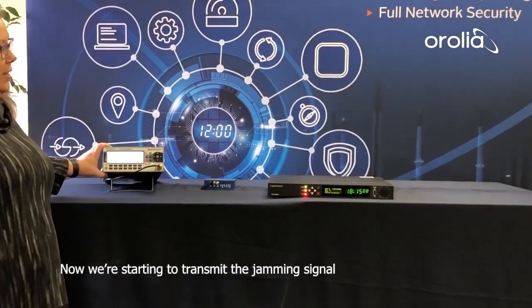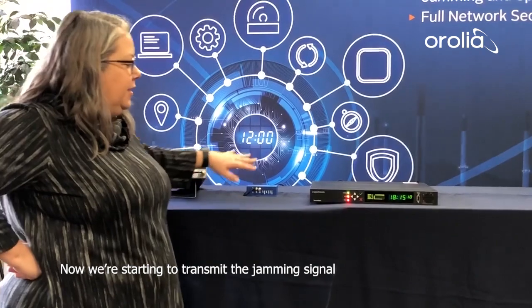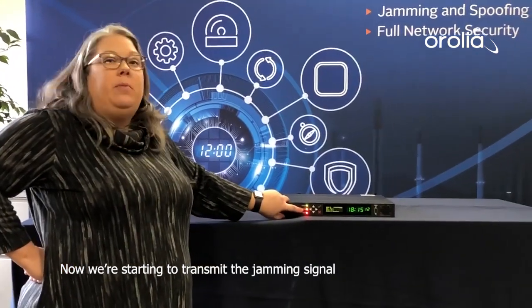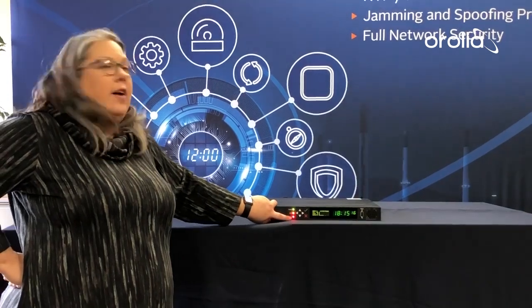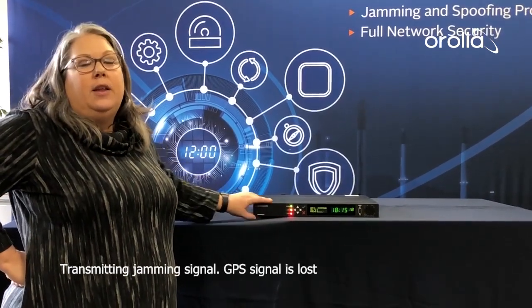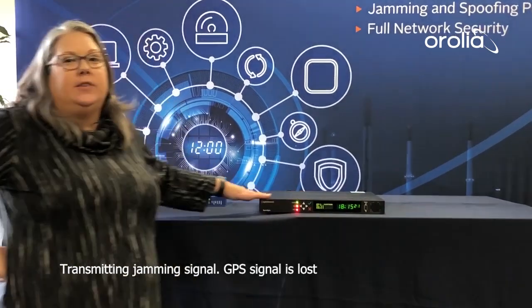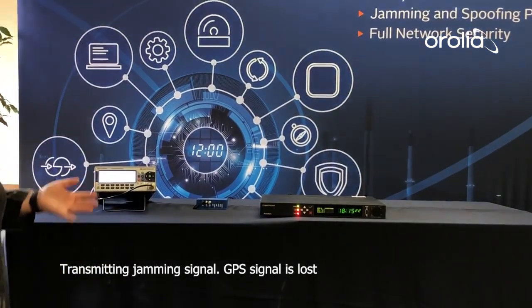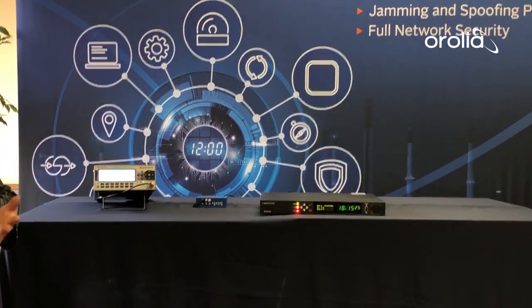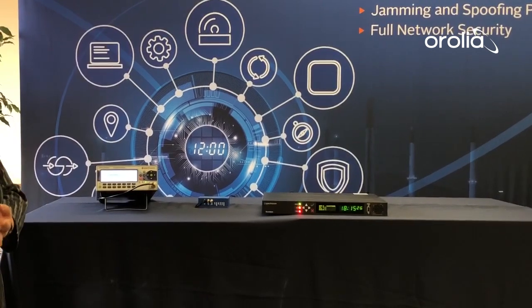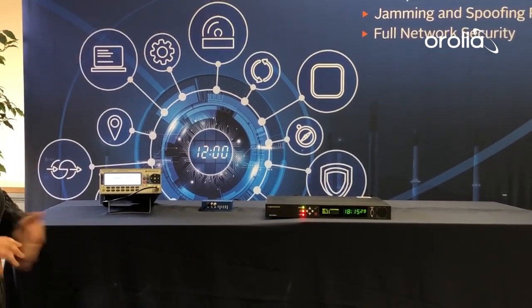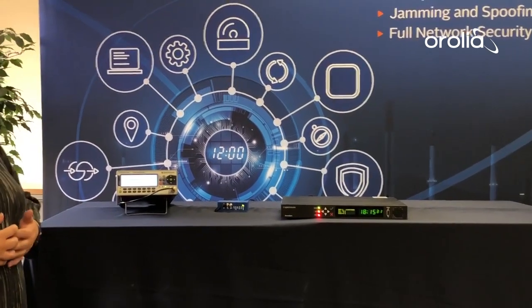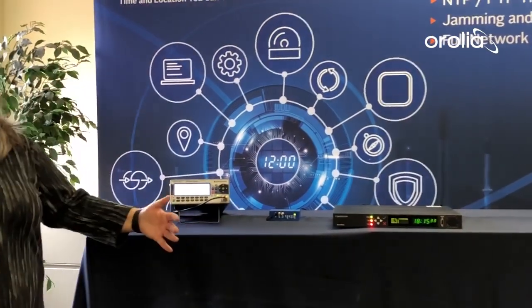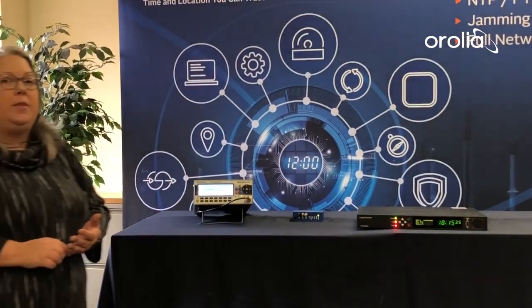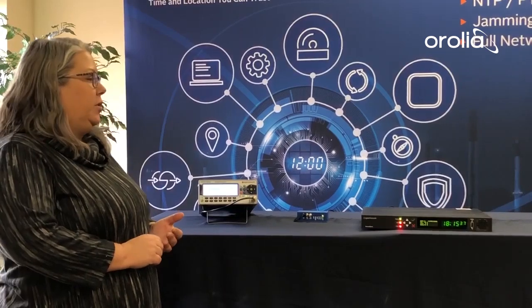So now we're just starting to transmit the jamming signal, and we can see here that we have a problem with our synchronization. It can't synchronize to GPS anymore, and there's a fault light letting us know that. Now the SecureSync will stay in this state as long as the jamming is present. There's nothing it can do about it. It detects it, it knows that it's lost GPS, it lets you know about it, and it does go into holdover, which still allows us to provide accurate timing for some amount of time. But if the jamming signal remains present, it's going to cause SecureSync a bunch of problems.